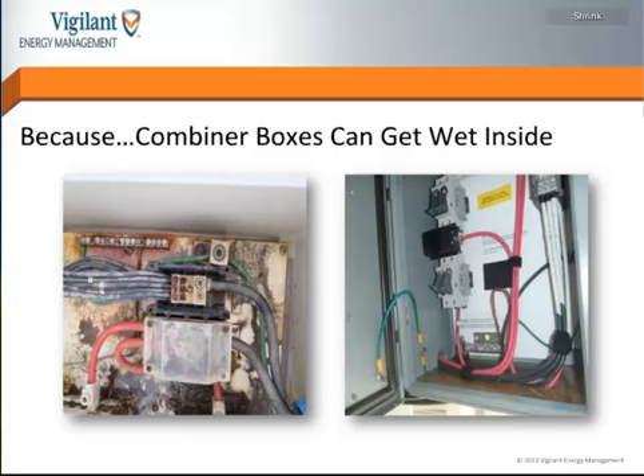We also find that combiner boxes have this bad habit of getting wet inside. And now these are NEMA 4 boxes that are watertight. So you might be thinking, all right, how is water getting in a NEMA 4 box? It shouldn't be in there. It's true, water should not get in NEMA 4 boxes. So how does it get in there? Well, it gets in there very commonly from condensation. These boxes are connected with conduit to some other part of the system. And if you're in moist and humid conditions, as we certainly have here on the eastern half of the United States, you can get moisture introduced through the conduit, and it migrates its way to a combiner box. And if that combiner box is cold, as compared to the ambient air, then you're going to get condensation inside. And it's amazing how much water can build up.